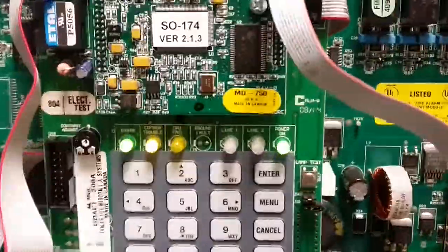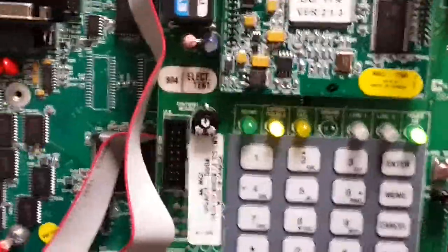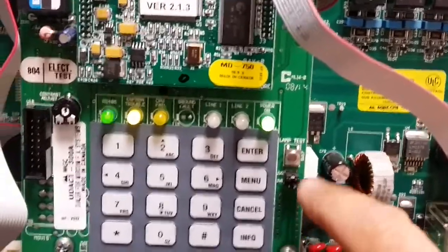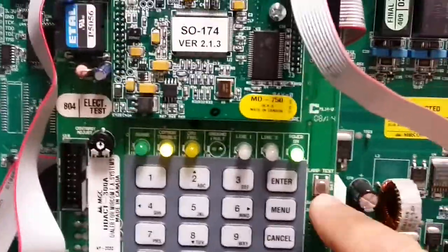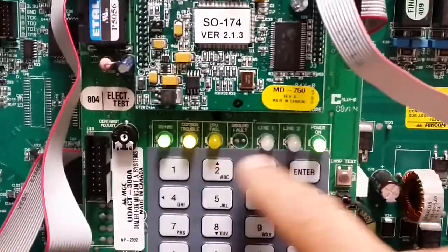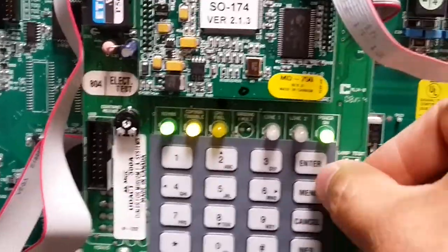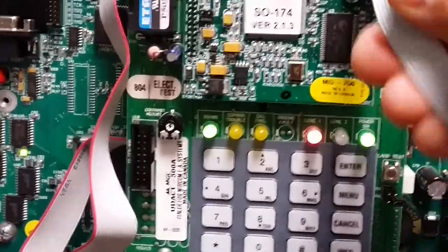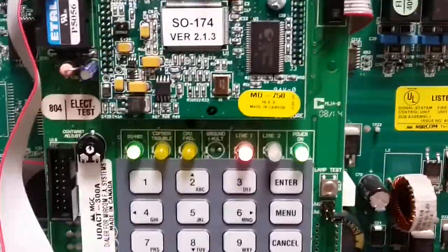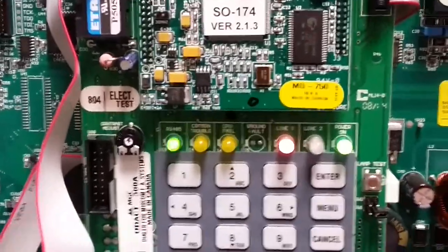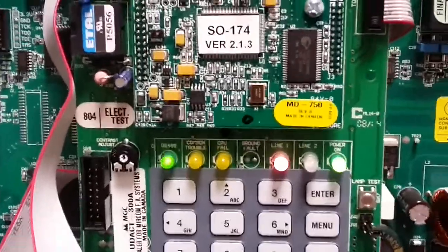One of the other things another guy and I noticed: if the phone lines are reverse polarity while JW2, the top jumper, is engaged like this, it won't tell you reverse polarity on the phone lines. The minute you disconnect, if you have reverse polarity, you would have a red light like that. It also goes red when it's active and talking to central station.